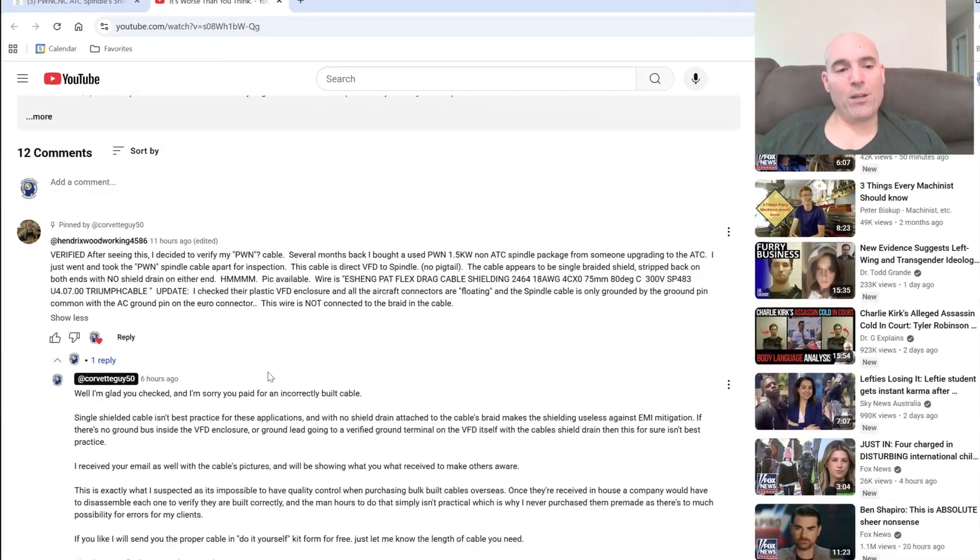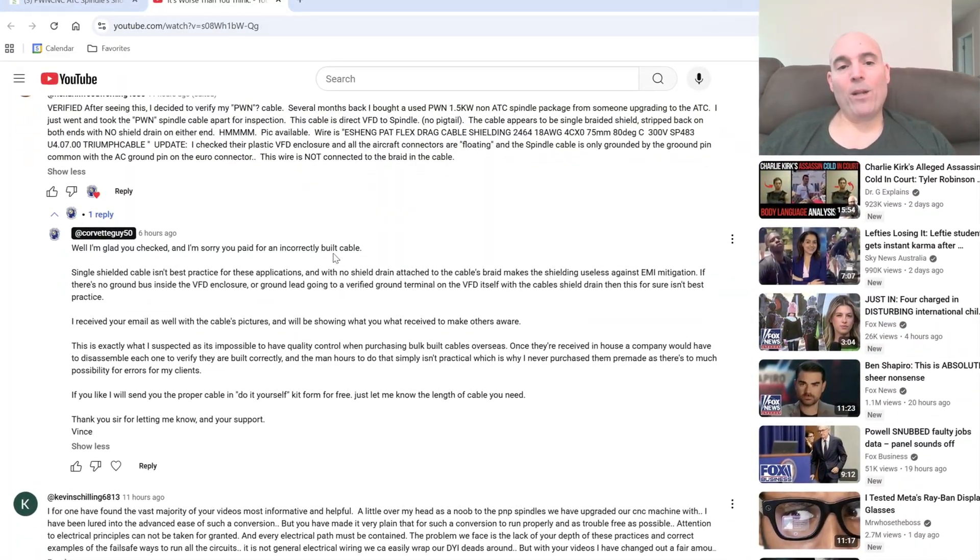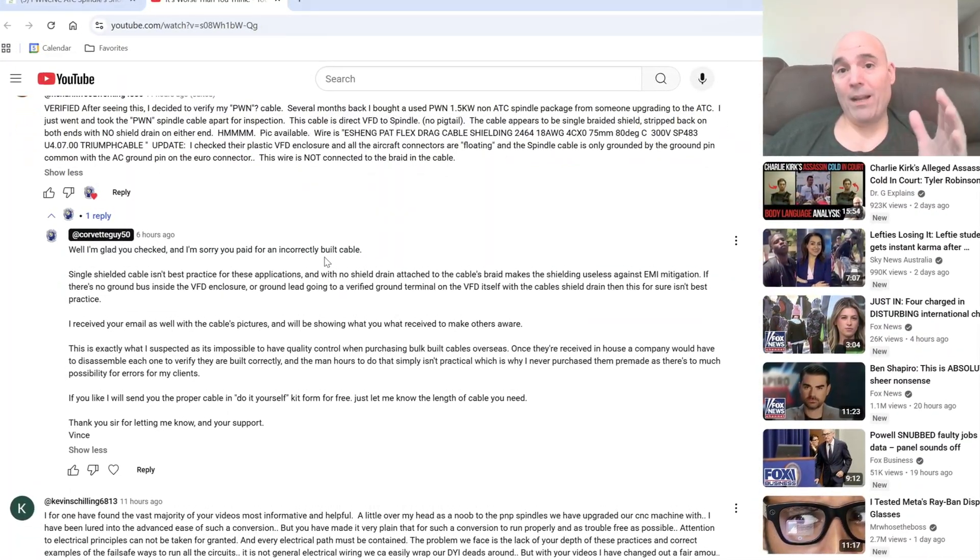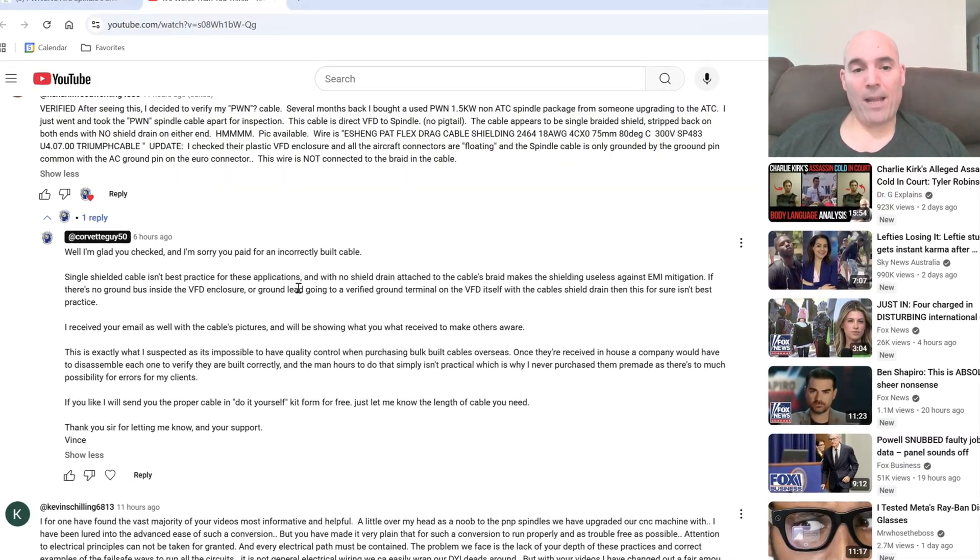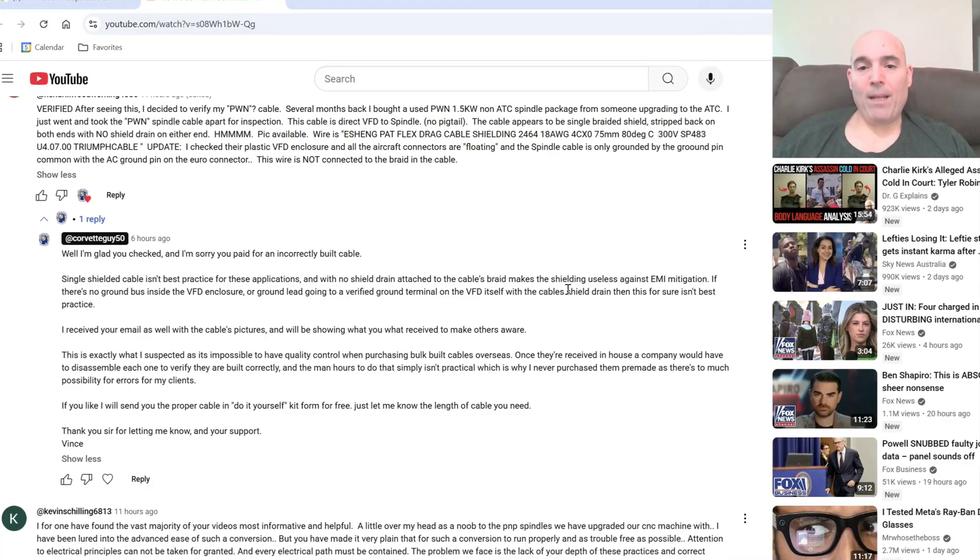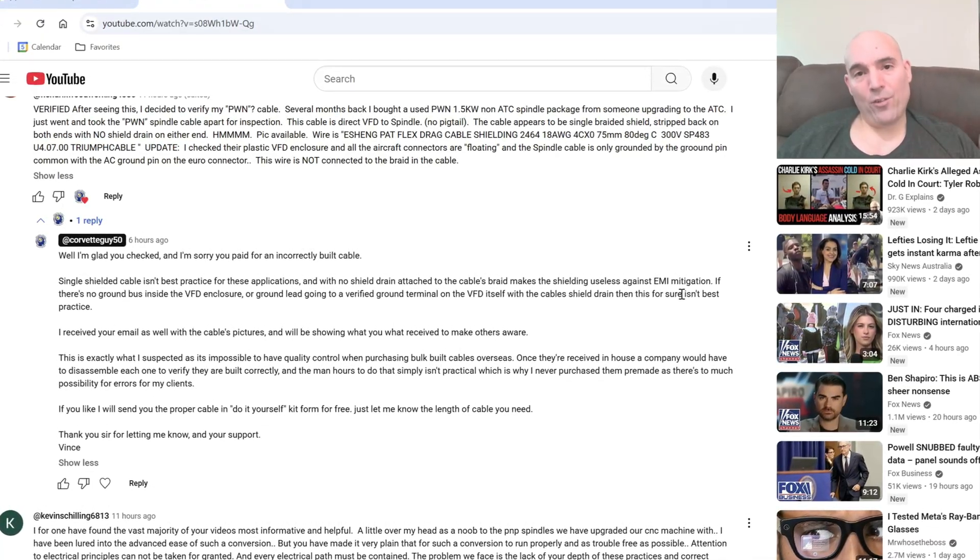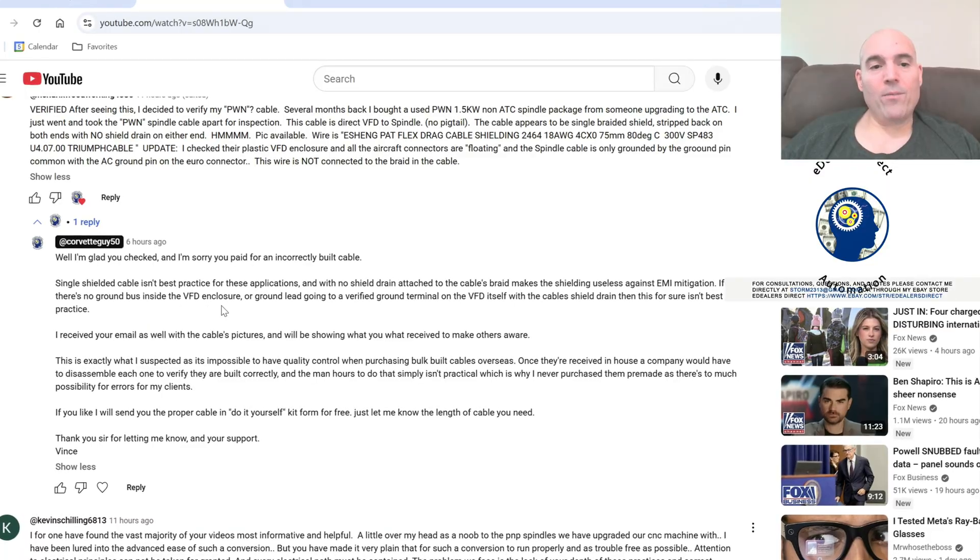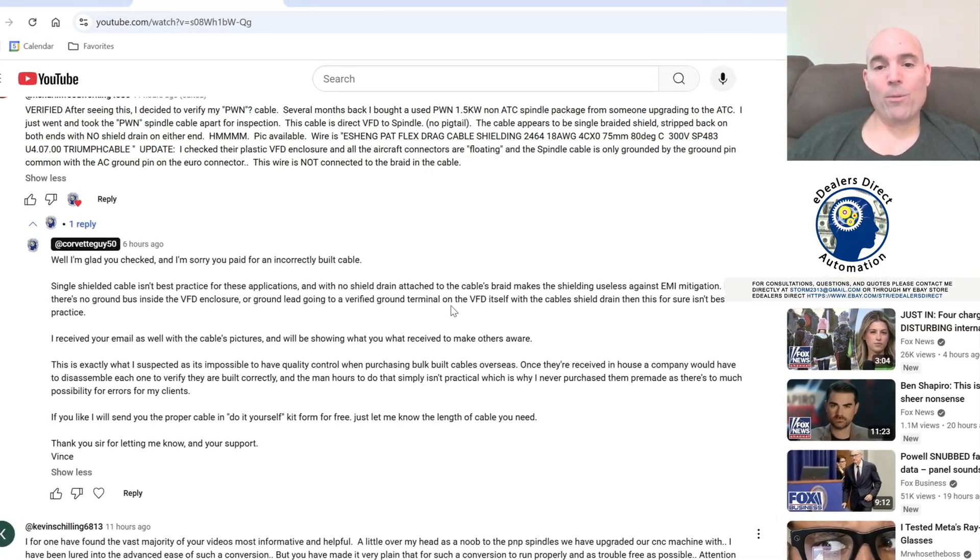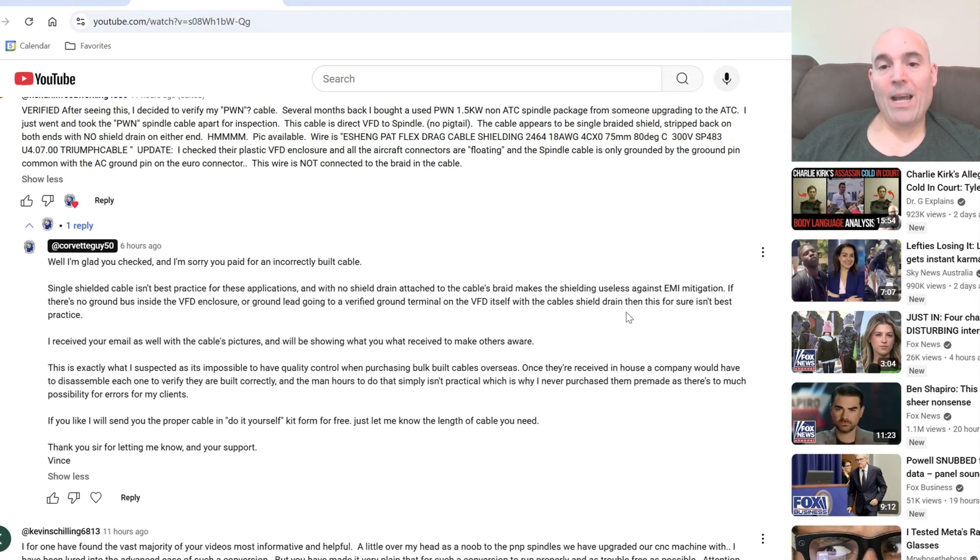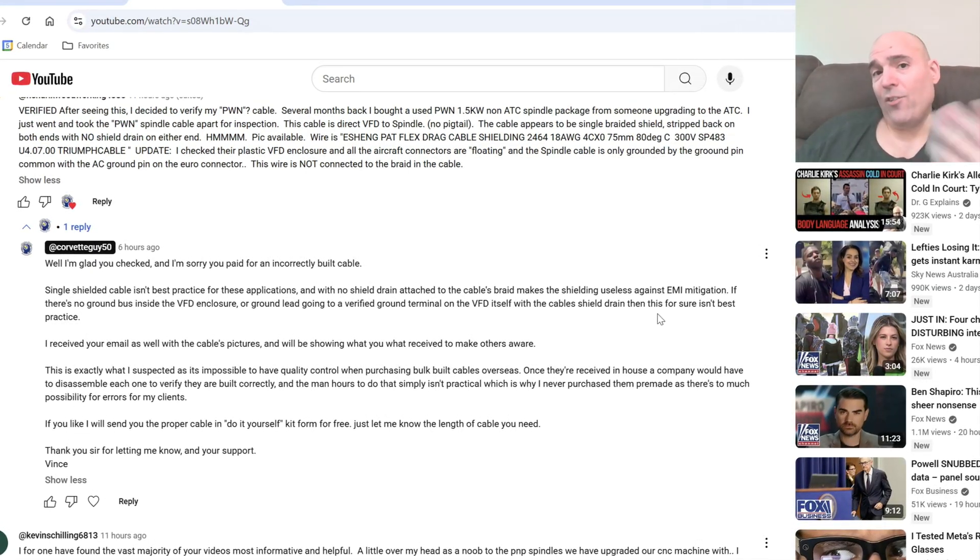My comment to this gentleman: well I'm glad you checked and I'm sorry you paid for an incorrectly built cable. I say that a lot, guys, and it is, it's really sad. Single shielded cable is not best practice for these applications, and when no shield drain attached to the cable's braid makes the shielding useless against EMI mitigation. This is fact. If there's no ground bus inside the VFD enclosure or ground lead going to a verified ground terminal on the VFD itself with the cable shield drain, then this for sure is not best practice as it's essentially a regular cable.